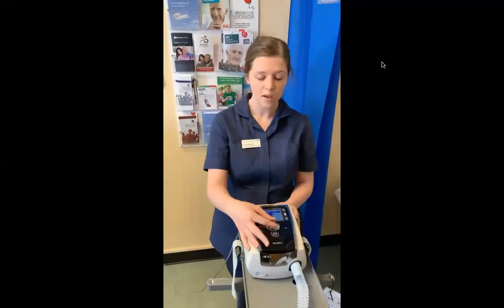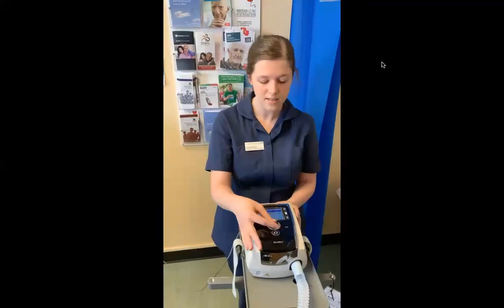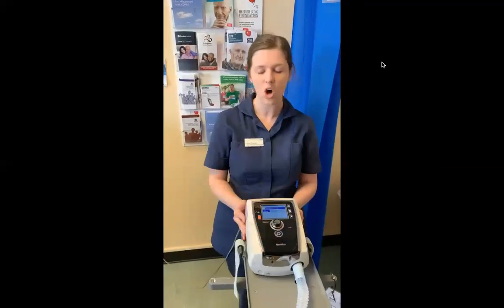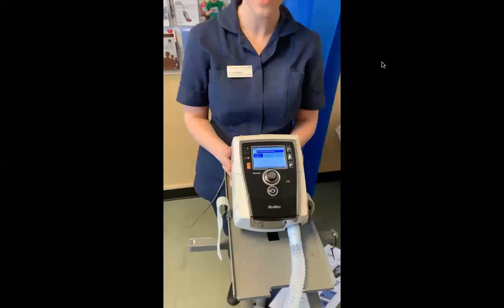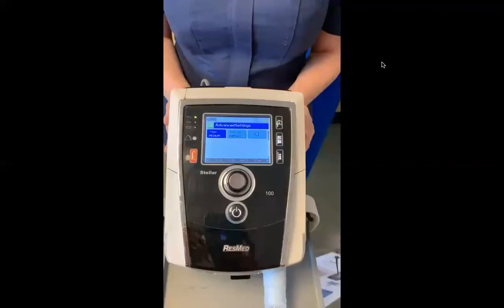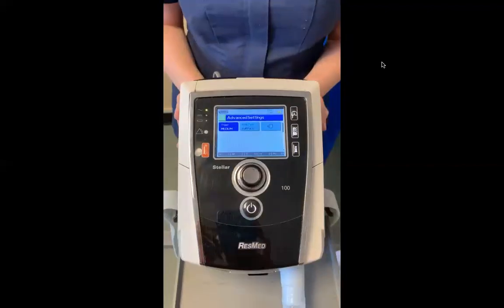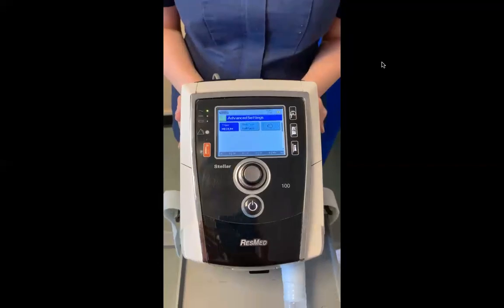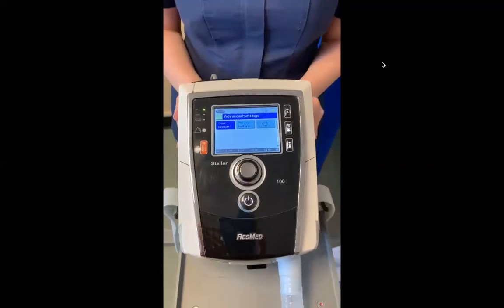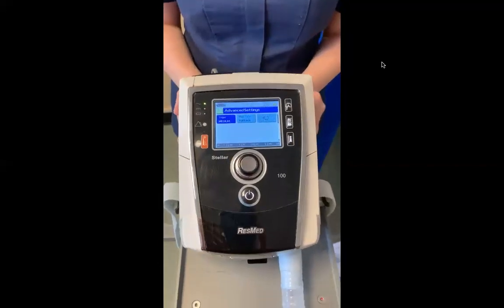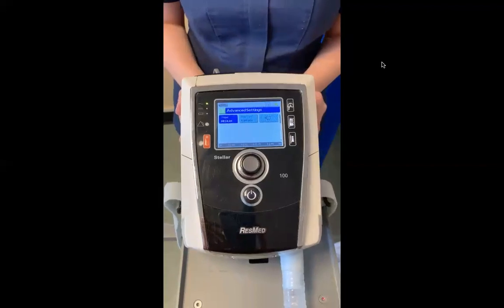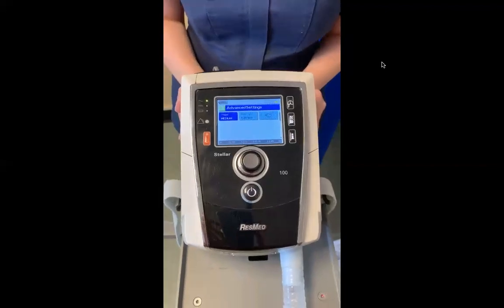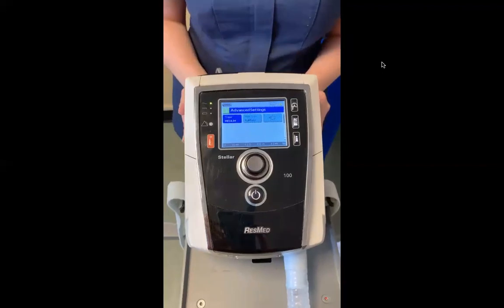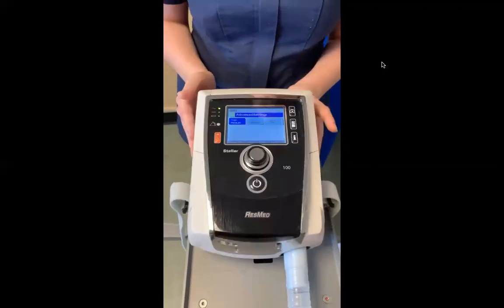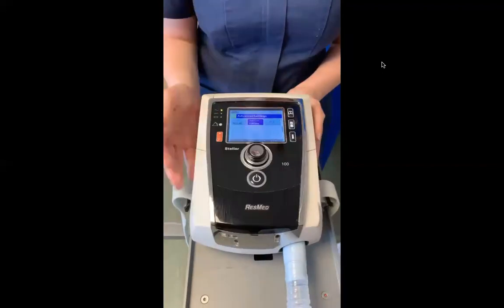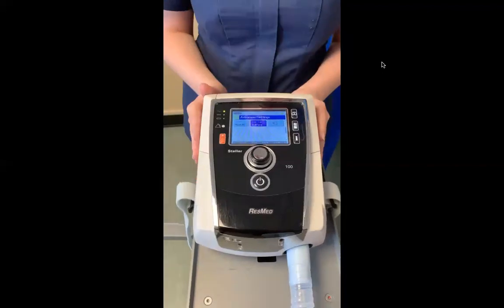The next setting is advanced settings, which really aren't advanced. So we have our triggers. The trigger is basically letting the machine know when the patient is inspiring and expiring, so it's giving them an idea so they can understand when to put a backup rate in. It's not really needed for CPAP, however, it's still there. So please just set at medium unless a respiratory consultant or registrar say otherwise. The next thing you can also do is the face mask, which we've already set on the front screen, so we don't need to change.